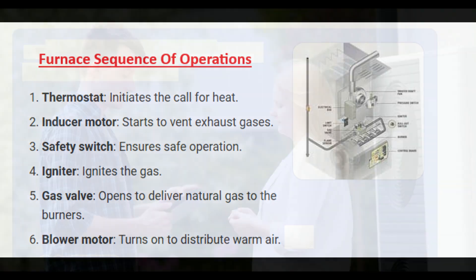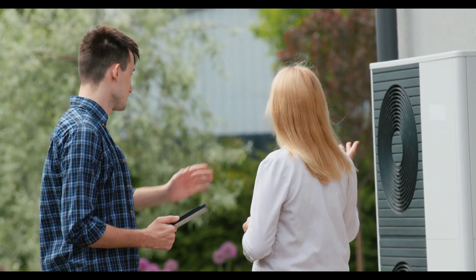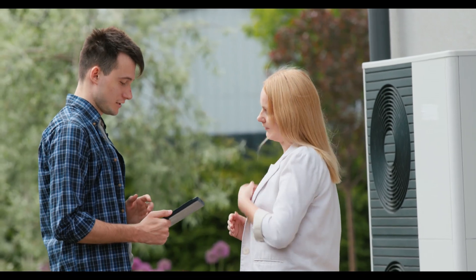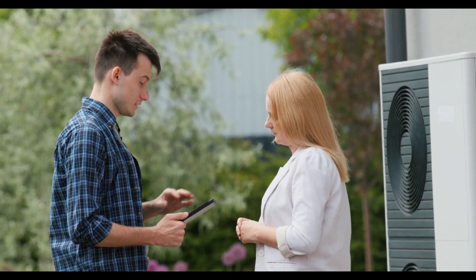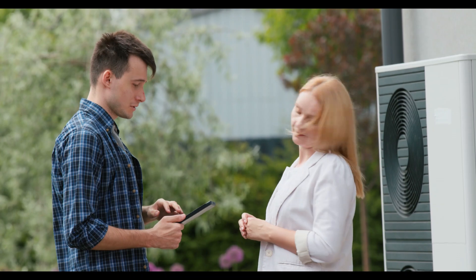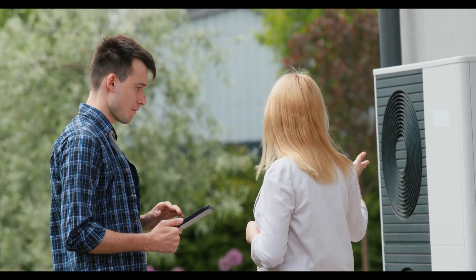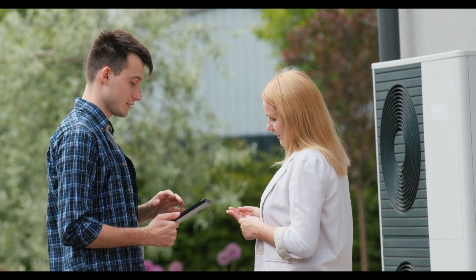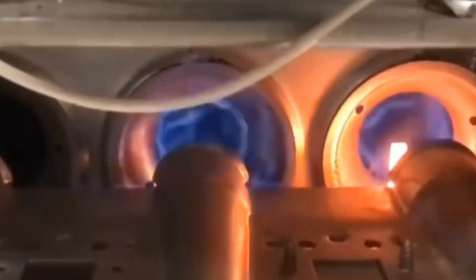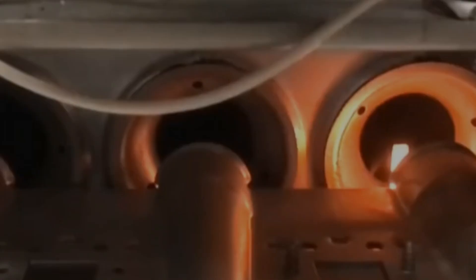I'll add a fourth tool aside from schematics, sequence of operations, and using your multimeter: actually talking to the customer and getting their feedback on what the problem might be. In a situation like that, I could walk in and the customer says the furnace starts up just fine, heats the house for five minutes, and then it shuts down. I'll know before I even walk up to the furnace that I may be testing that thermal overload switch. So that's another tool as well.